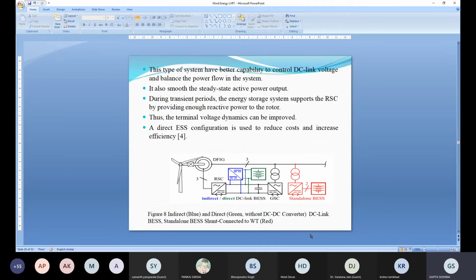Another configuration is this direct configuration, where the battery is directly connected to the DC link voltage, so it can supply the energy to the DC link capacitor, or it can take energy from the DC link capacitor as and when it is required.